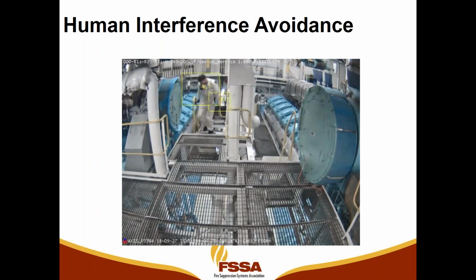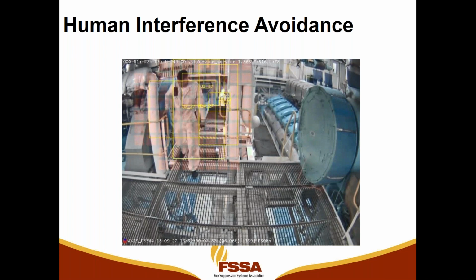Video analytics have been complemented with human recognition. In this case, there are 2 human recognition algorithms added to the smoke detection algorithm to avoid false alarms for smoke from people moving close to the image. You'll see the yellow outline and the orange tiles. Those are the 2 human recognition algorithms that avoid false alarms for oil mist or smoke with people moving around in these small spaces.